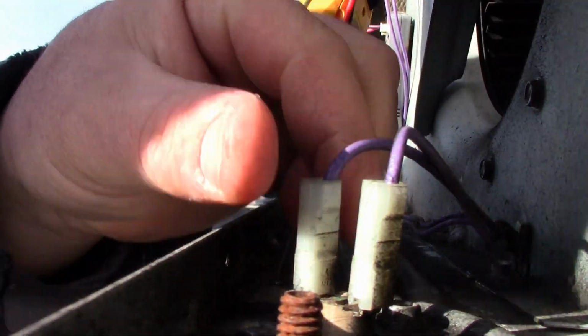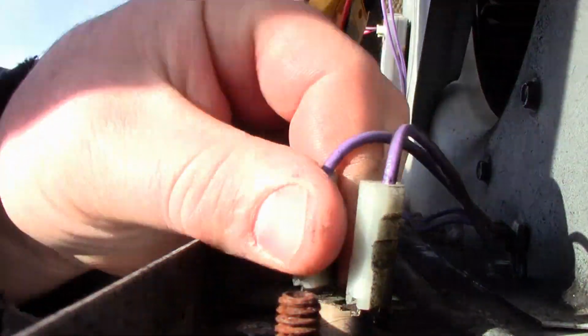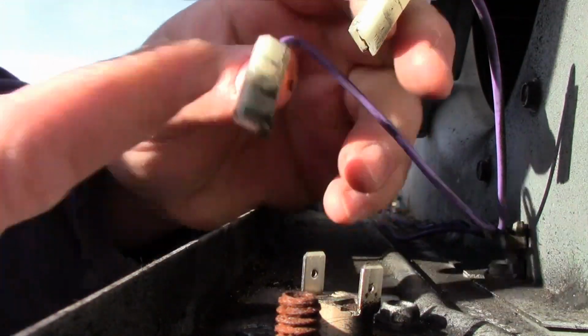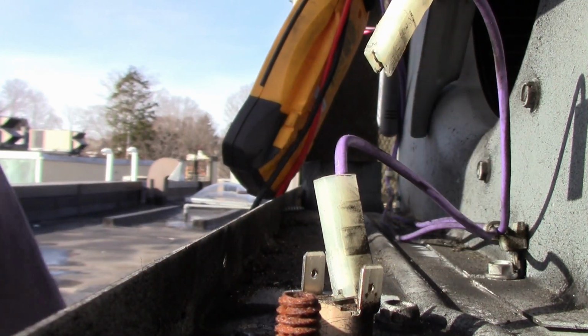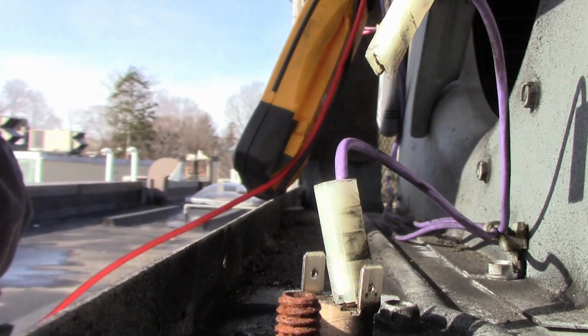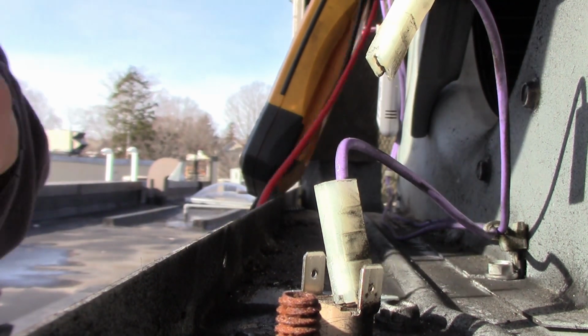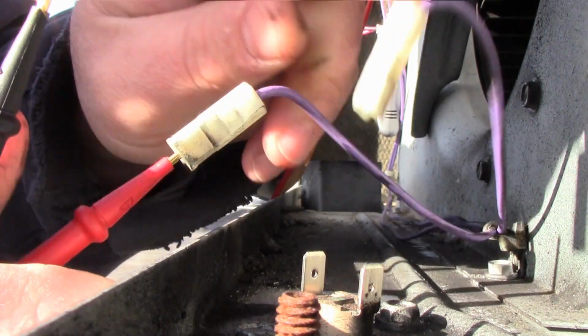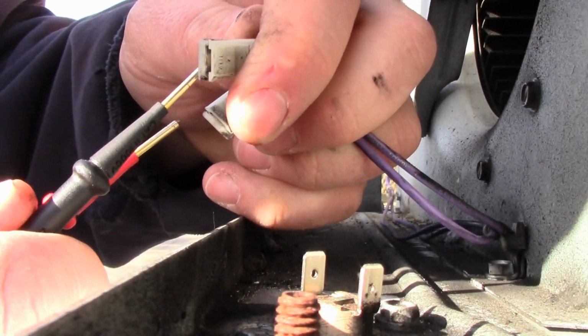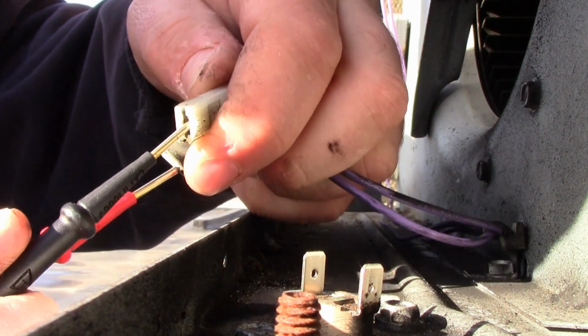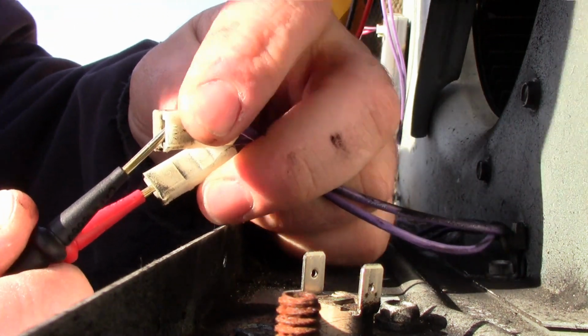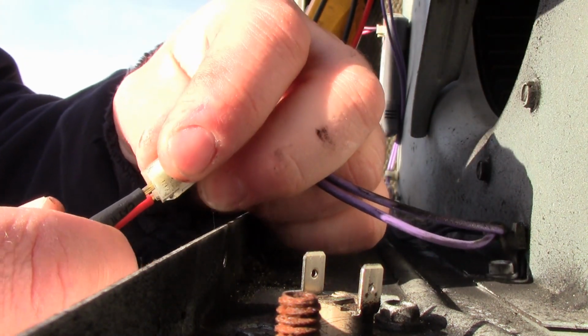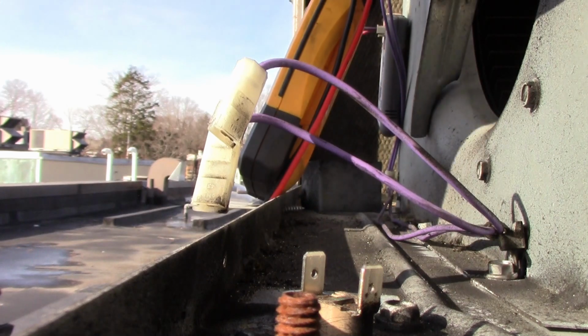Okay, so I'm ready to check this limit switch. I'm going to pull these two wires off just to make sure that if we were to check these two here, every other switch in the circuit, actually the centrifugal switch, is going to be closed, so that isn't going to do anything.